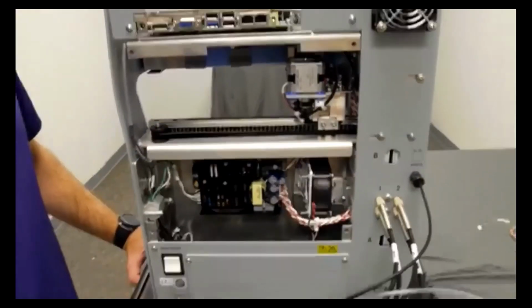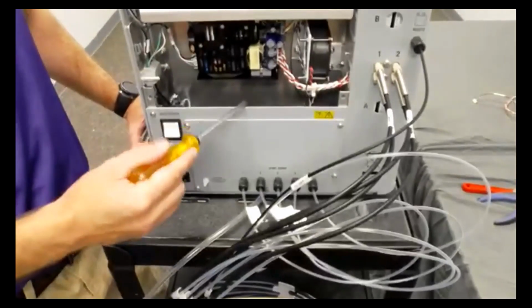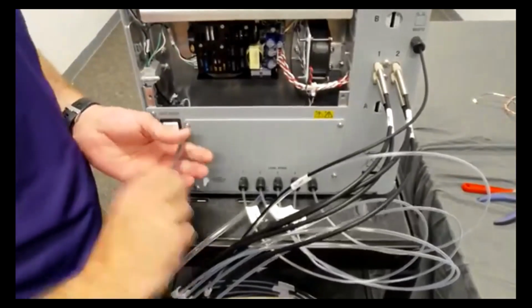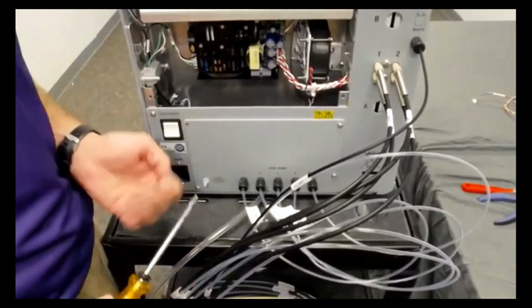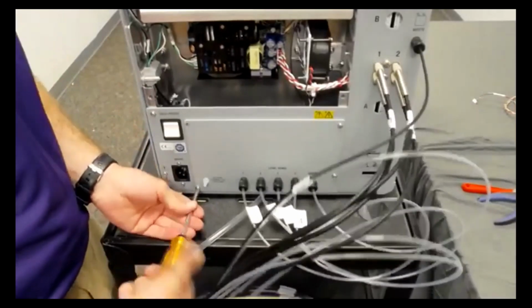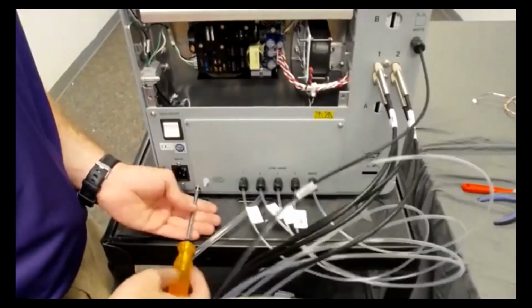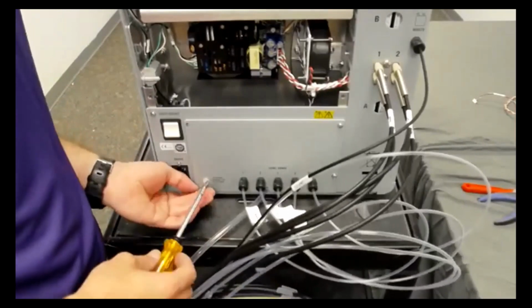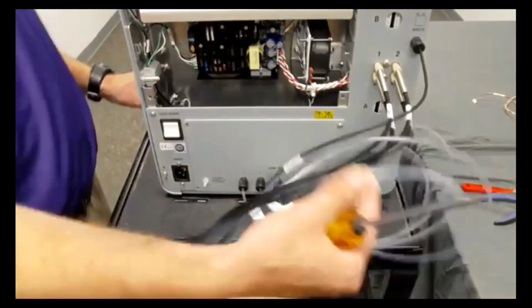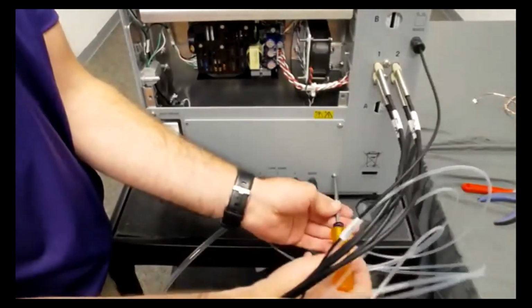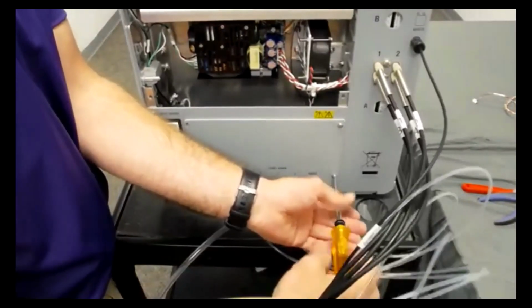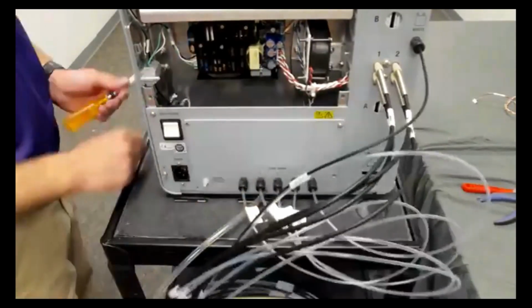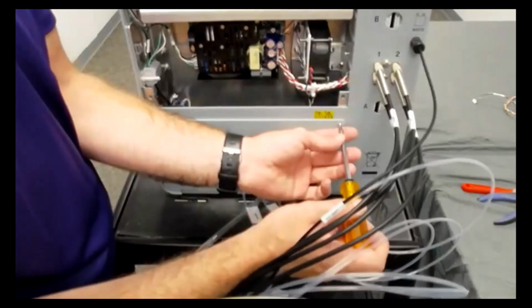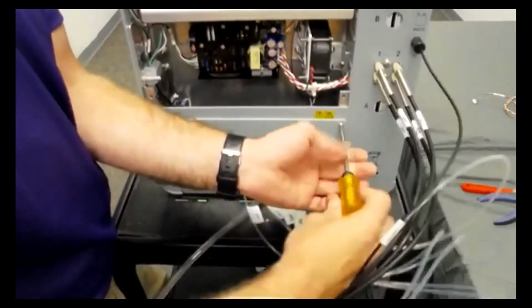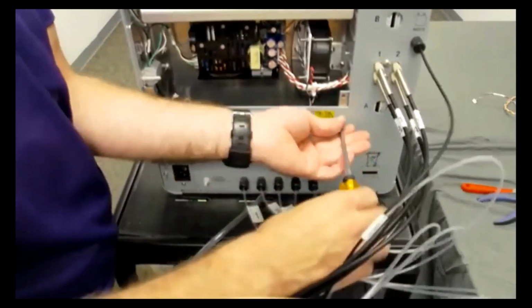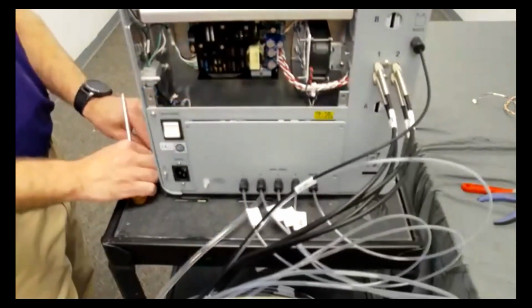Now the other panel down here, this is for your air supply if you have one. So it's the same 4 screws. How it works is we have an air pump down here. This pumps a small amount of air into your clear lines for your inlet lines. That's going to generate bubbles. And the machine takes a reading of how much air pressure is needed to generate those bubbles. And through a mathematical equation, tells the unit you have this much volume in that container in centimeters. And that's a reading that you can see on the unit itself.